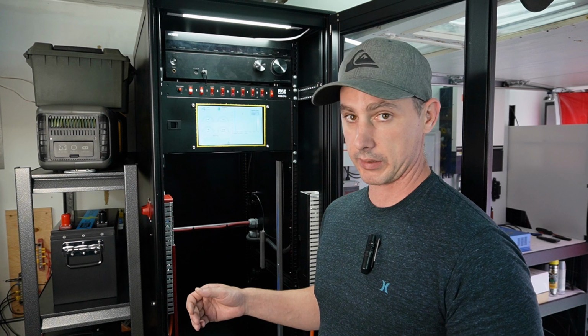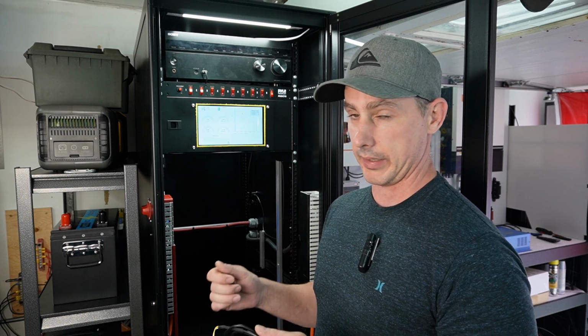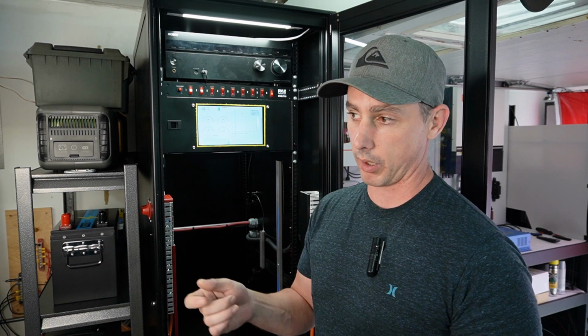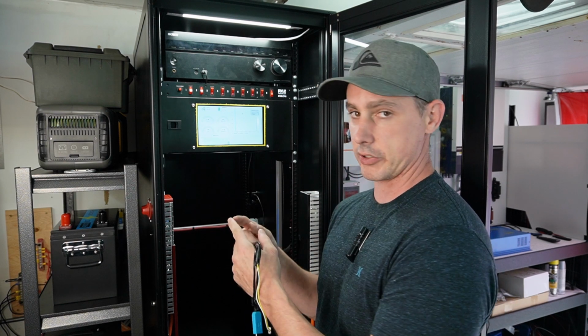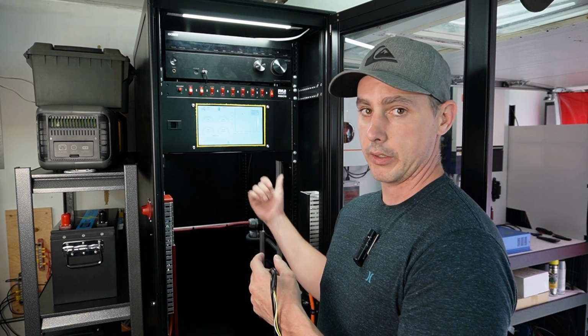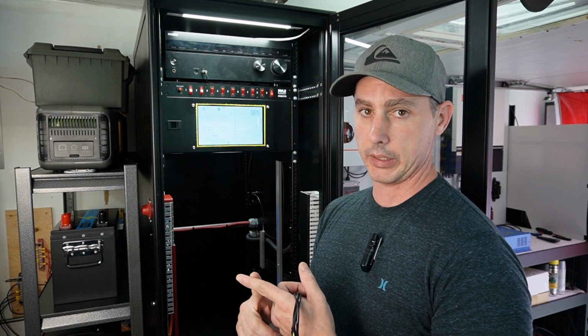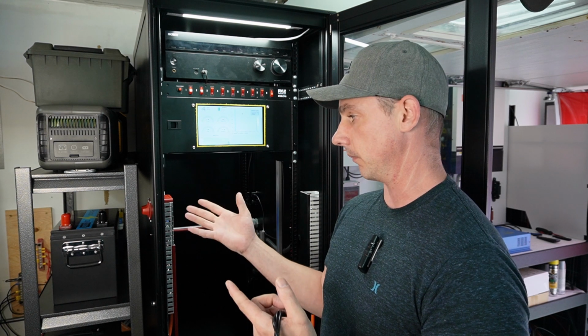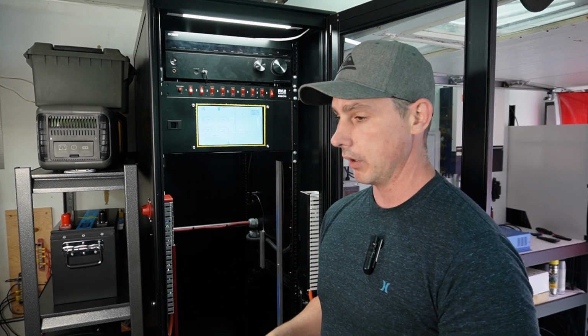I ended up disconnecting all the batteries and then checking with the continuity. So continuity is if you have a connection. So I went from the negative bar to the metal case, checked continuity, and there was continuity from case to negative bar, which is not right.